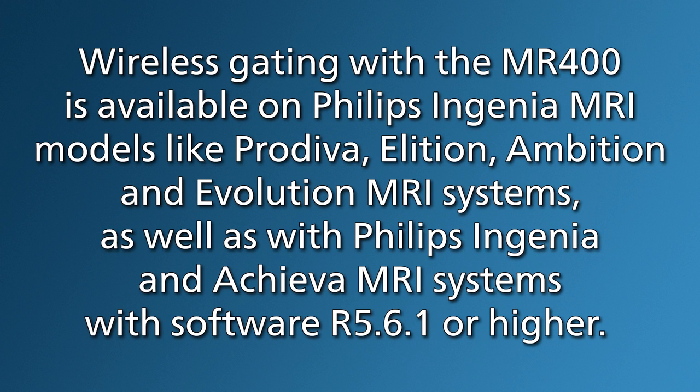Wireless gating with the MR400 is available on Philips Ingenia MRI models like Prodiva, Elition, Ambition and Evolution MRI systems, as well as with Philips Ingenia and Achieva MRI systems with software R5.6.1 or higher.